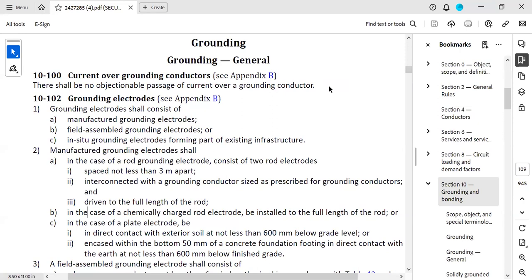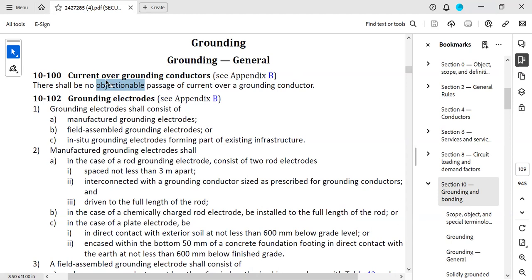Accidental loosening or disconnection of the neutral conductor can occur at a grounded main service, and that's going to also cause objectionable current flow that you're not allowed to have according to Rule 10-100. Those neutral currents that flow in grounding conductors are considered objectionable, and corrective action has to happen right away.